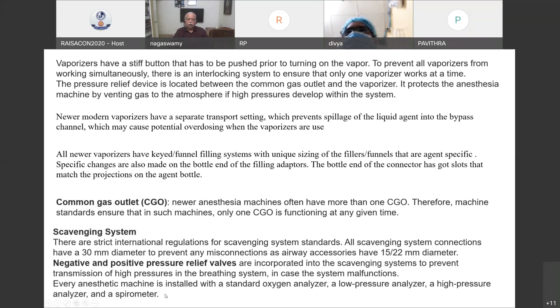And every anesthetic machine nowadays is installed with a standard oxygen analyzer. And there is a low pressure analyzer, a high pressure analyzer, a spirometer, everything is there. And exhaled gas analyzers are also included. Then coming to mandatory monitoring systems, which should be available in all the anesthesia machines in the modern workstation: ECG, blood pressure cuff, pulse oximeter, CO2 and end-tidal CO2 monitor, tidal volume and airway pressure monitor. All these things come automatically.